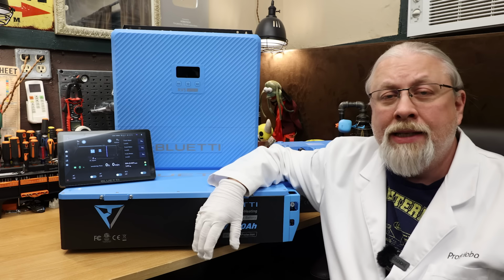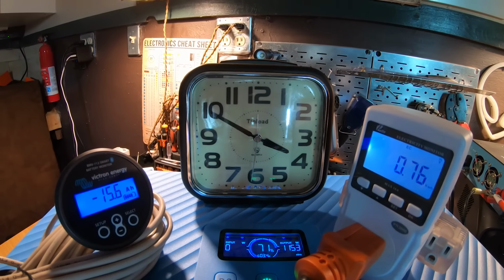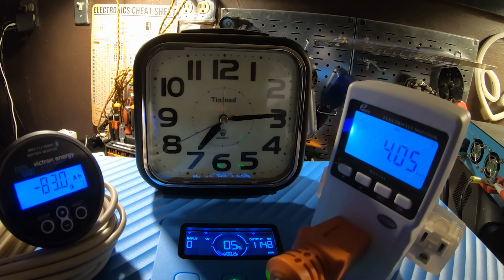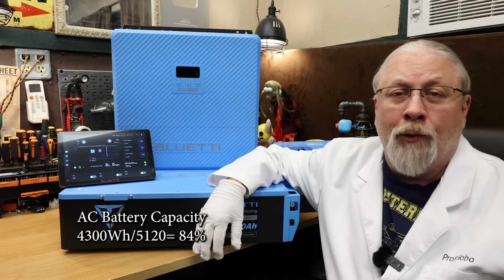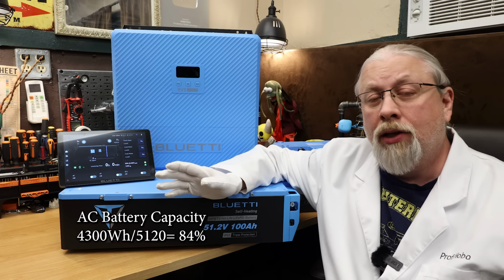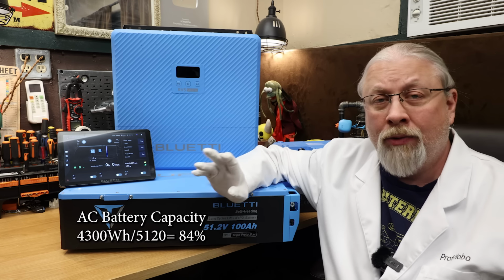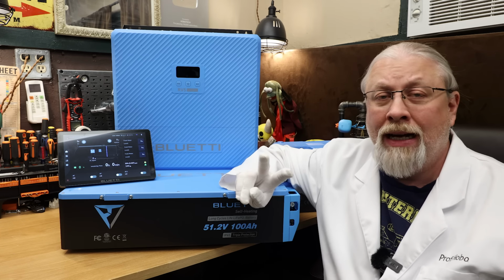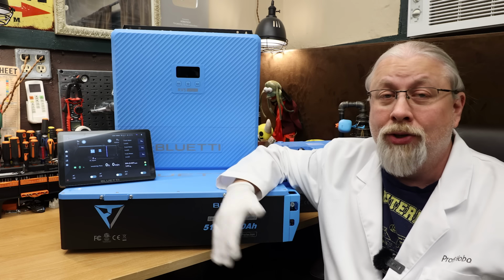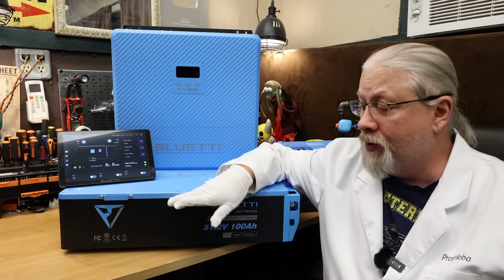As for the results of the AC battery capacity test, it scored an even 4,300 watt hours out of 5,120, for 84%. That's on the low side of average. I actually ran this test twice to verify, and this was the better of the two results after 2 full cycles of the battery.